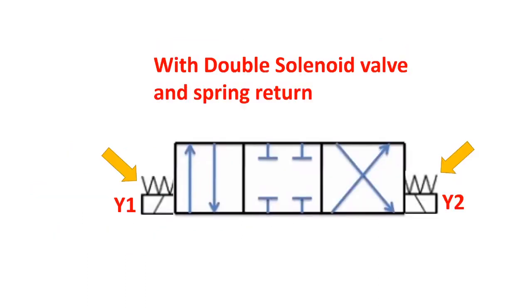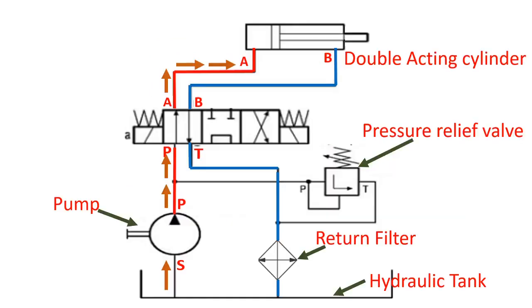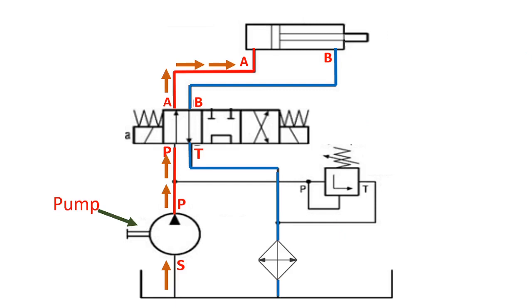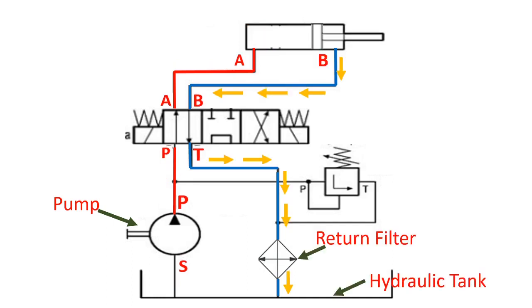Let's start with the piston extending. When solenoid one is activated by an electrical signal, the pressurized oil generated by the pump passes through the normally open ports of the directional valve and enters port A of the cylinder. The piston moves from left to right. The oil on the piston-side port B automatically returns to the oil tank via port B of the cylinder, through the directional valve, through the filter, and back to the oil tank.